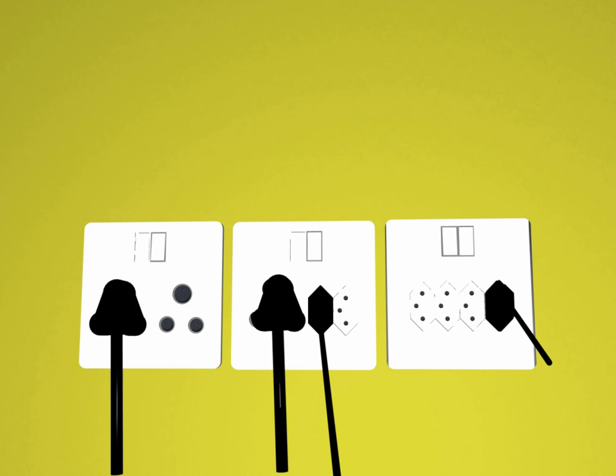The IEC 60906-1 system also avoids the problems of the Schuko and French systems currently used in most of Europe and large parts of Asia. Since the Schuko plug is non-polarised it can be inserted upside down, and therefore electronic equipment with Schuko plugs must be fitted with double pole switches and fuse links on both the line and neutral pins in order to be safe. Requiring these extra safety features can add to the manufacturing costs of electronic equipment.